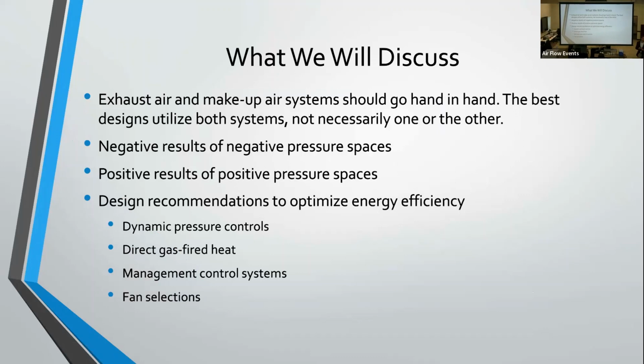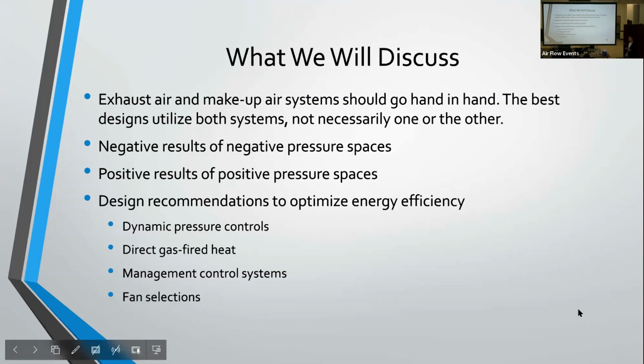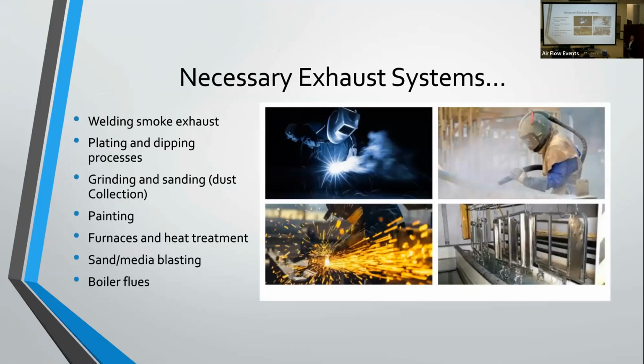We're going to be looking at the negative impacts of negative pressure spaces, the positive impacts of positive pressure spaces, and also some design recommendations to optimize your efficiencies, such as dynamic pressure controls, direct gas fired heat, management control systems, and fan selections, specifically fan types. As we all know, there are hundreds of processes out there that all require some type of capture exhaust system, whether it's welding, painting, dipping, or grinding.